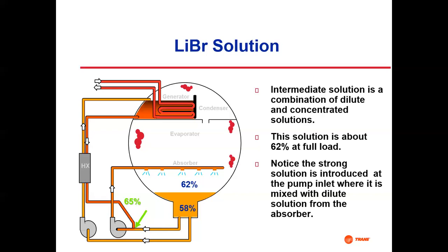Now, that's a rate, right? We can talk about an amount if we want to talk about an amount of cooling. We talk about 1 ton hour. That would be 12,000 BTUs per hour times 1 hour, which gives 1 ton hour, and that's 12,000 BTUs as an amount.